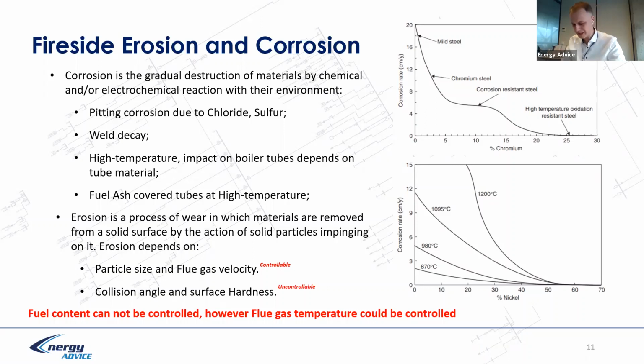Later, after analysis, we can change the supplier of a fuel, because maybe this supplier's fuel has high chloride or sulfur. We can do this, but during the period when the fuel is burning, during these seconds and minutes, we cannot change the content of the fuel.